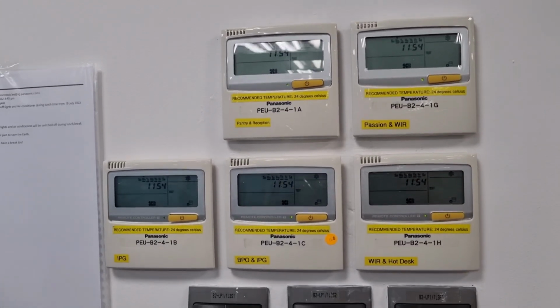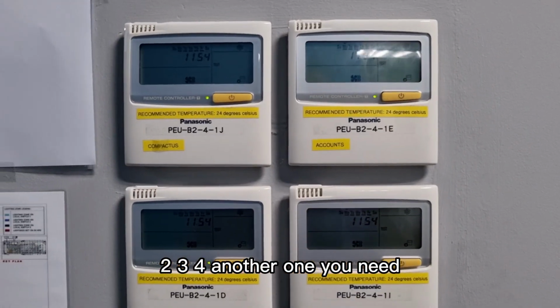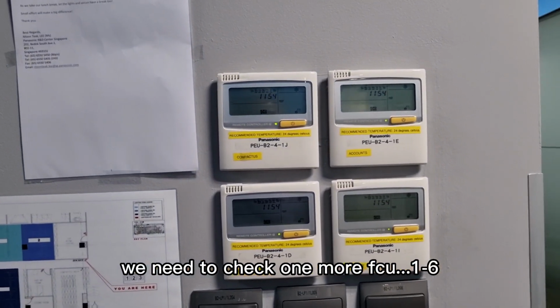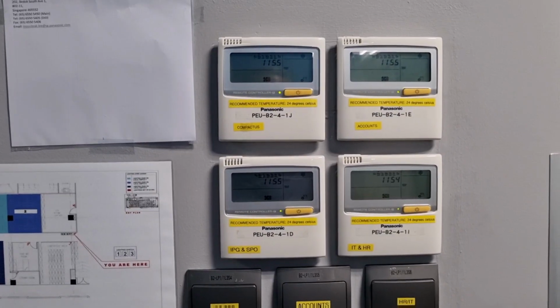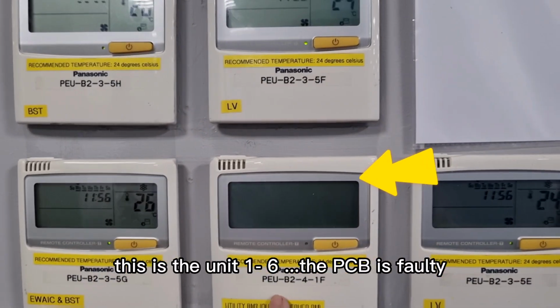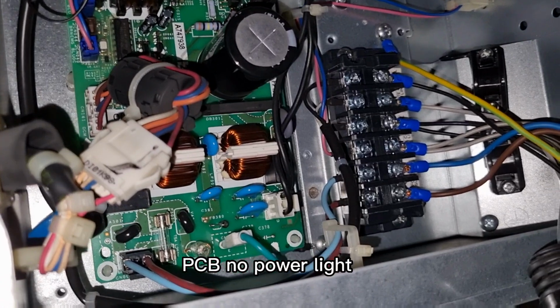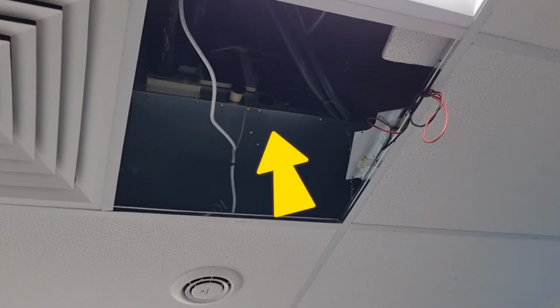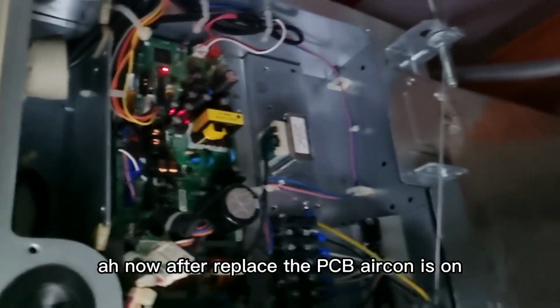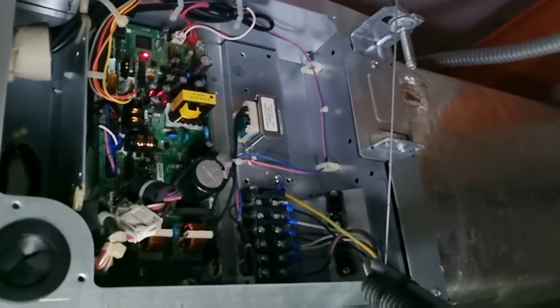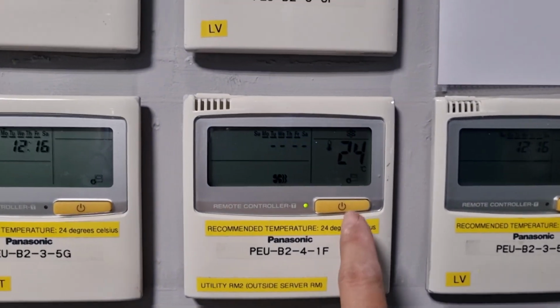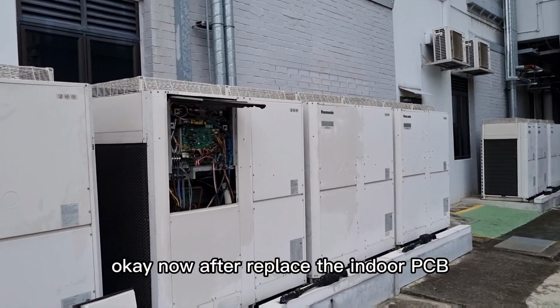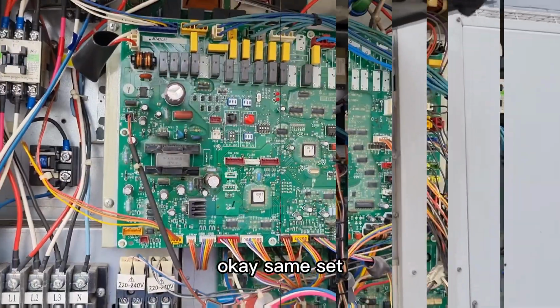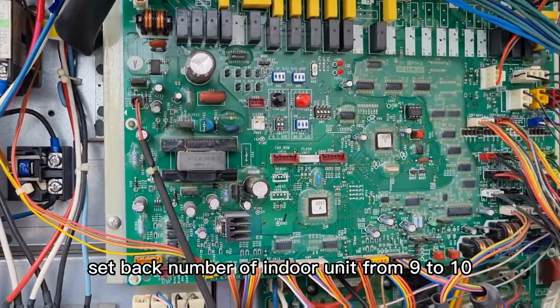Yeah, okay. Indoor. 2, 3, 4. Another one unit. We need to check that 1-6. This is unit 1-6. This is unit 1-6, the PCB is faulty. Now after replacing the PCB, aircon is on. Okay, now after replacing the indoor PCB, still the same, off the power supply. Okay, same, set back the number of indoor units from 9 to 10.